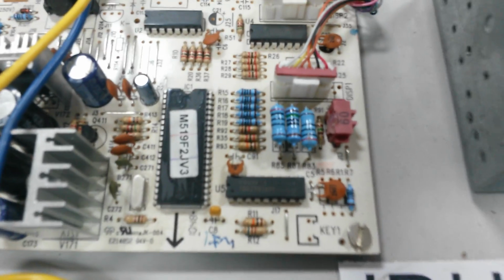Now just to give you a glimpse, if we come to our sensors, these are also provided the same kind of voltage. These sensors are negative temperature coefficient, that means NTC type sensors. So what does NTC mean? Whenever there is a change in temperature, if temperature reduces, resistance increases, and whenever temperature increases, resistance decreases, which clearly indicates they are inversely proportional to each other. So change in temperature leads to change in resistance.